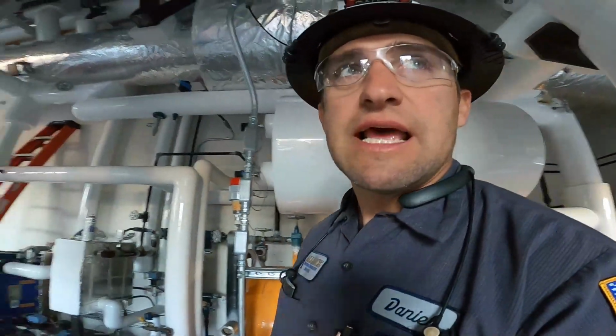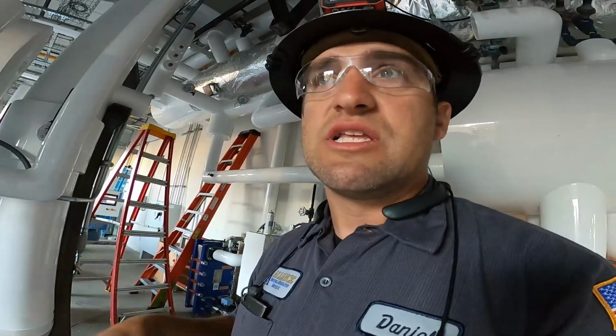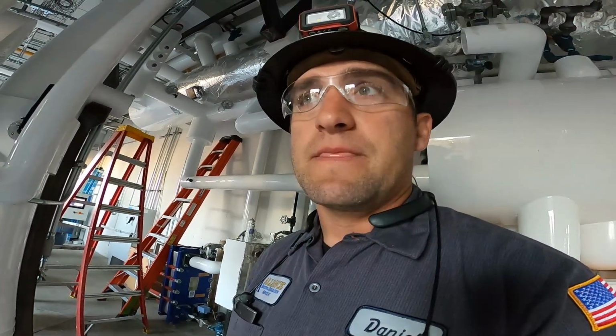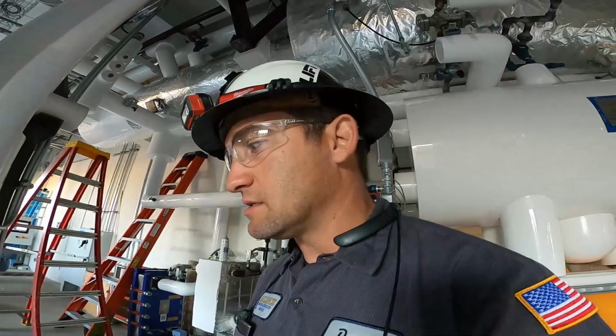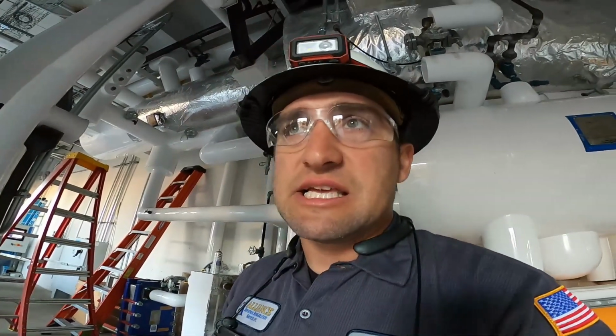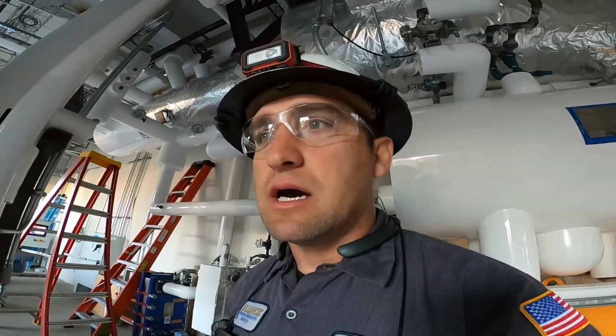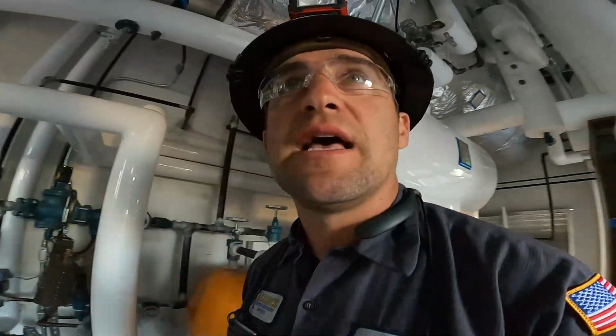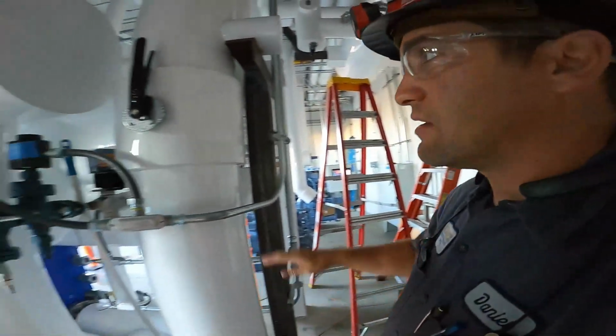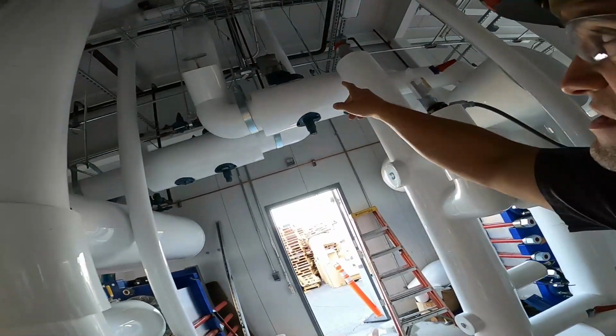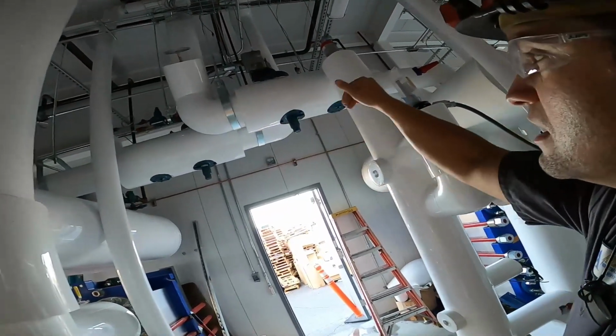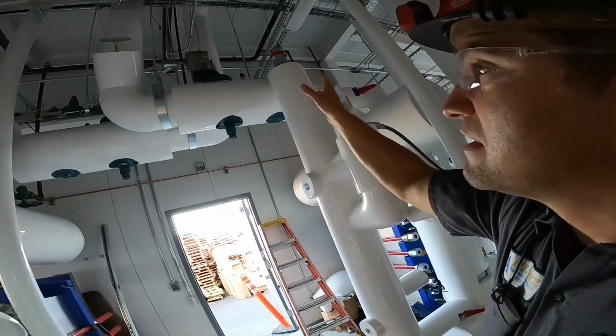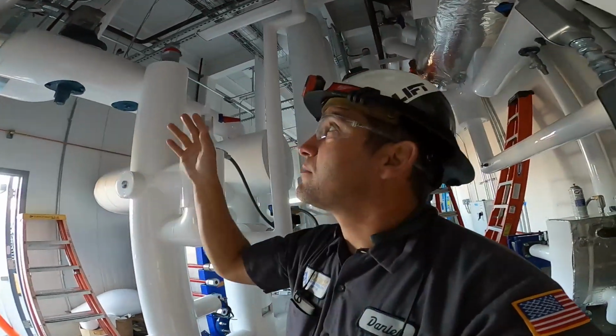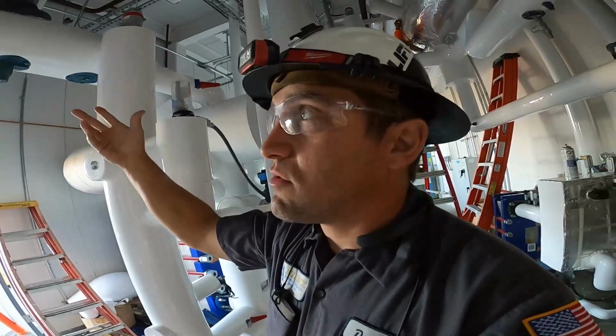If your system does shut down, it shuts the auto purge off, because it will continue to purge if your system shuts off. Because you have no discharge, it equalizes, the gas stays in there, and it thinks it has a liquid until you lose pressure, then it will shut down. But it might think it has vapor in it. So we're going to get ready to turn these heat exchangers on here. We've got these big suction modulating valves, motorized valves. They fully open. They're pilot assisted to take out the 2-pound pressure drop across the valve. So when they run, they can run fully open.